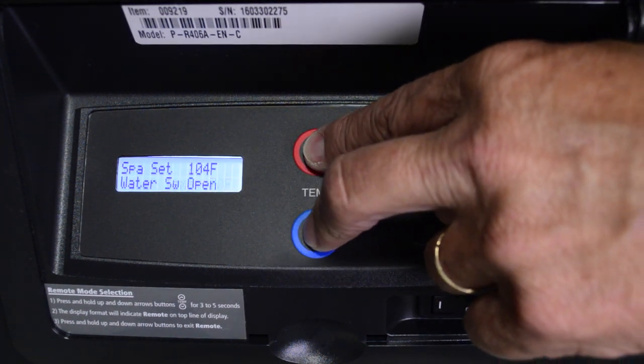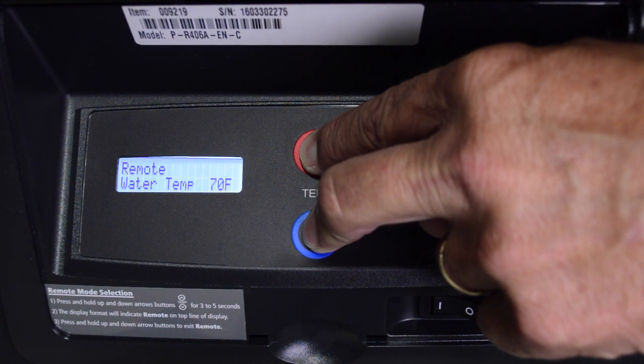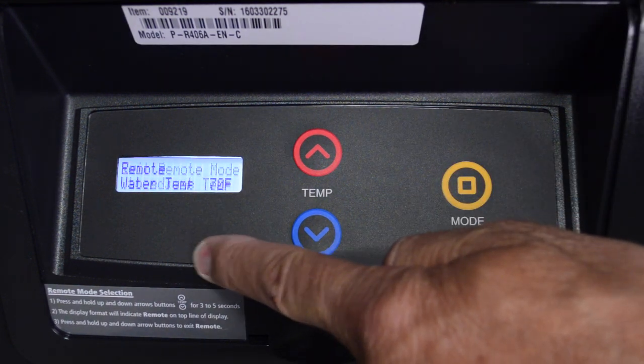The actual set point will be controlled by the remote control. To activate or deactivate the remote function, press and hold the up and down arrow buttons for three to five seconds. The top line of the display will alternate even when the unit is off with no demand. Remember, when the heater is in remote operation, the keypad mode and temp buttons are disabled.